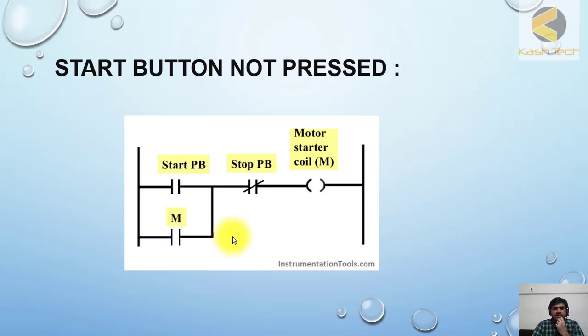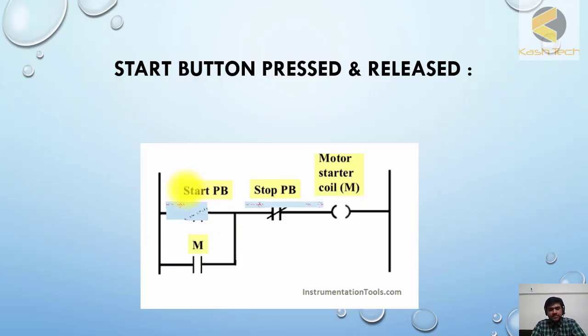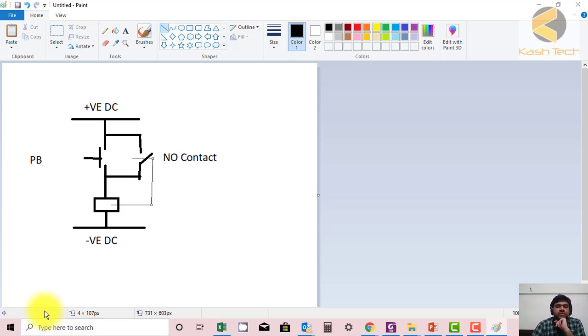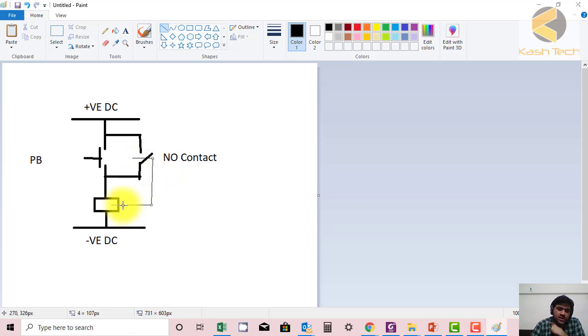Okay, this is another way to show how the circuit is drawn — another presentation. Now I have drawn a very simple circuit because the previous circuit was a little bit complicated to explain how seal-in contacts are working. Here you can see I have a contactor or an auxiliary relay, and what I did is I used the normally-open contact of this relay — this is the NO contact of this auxiliary relay — in parallel with the push button.